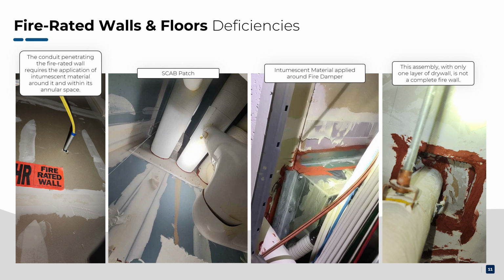What's wrong there? Well, most fire-rated walls consist of two layers, the drywall attached to the supporting stud, and a second layer of drywall. So in this picture, it has only one layer? Correct. That reduces the rating to a maximum of 30 minutes, while a full hour is expected for compliance. And that's all above the ceiling that most of us don't even think about.